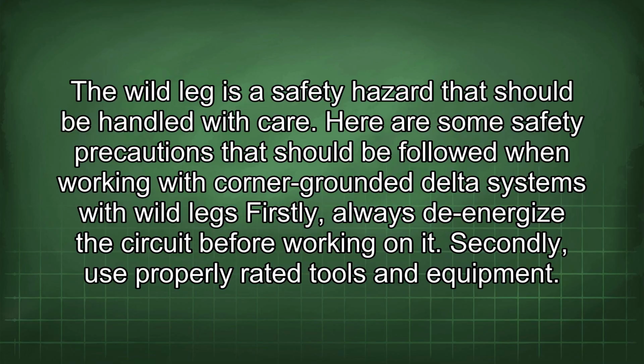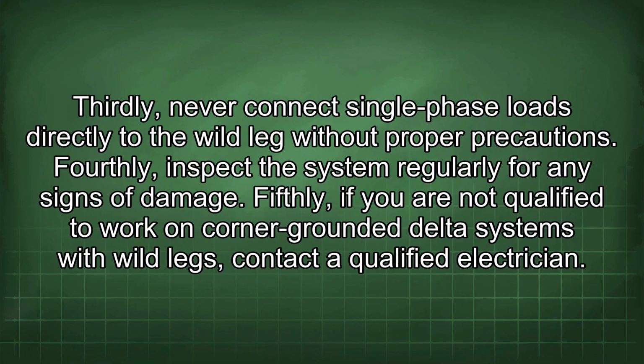Here are some safety precautions that should be followed when working with corner-grounded delta systems with wild legs. Firstly, always de-energize the circuit before working on it. Secondly, use properly rated tools and equipment. Thirdly, never connect single-phase loads directly to the wild leg without proper precautions. Fourthly, inspect the system regularly for any signs of damage. Fifthly, if you are not qualified to work on corner-grounded delta systems with wild legs, contact a qualified electrician.